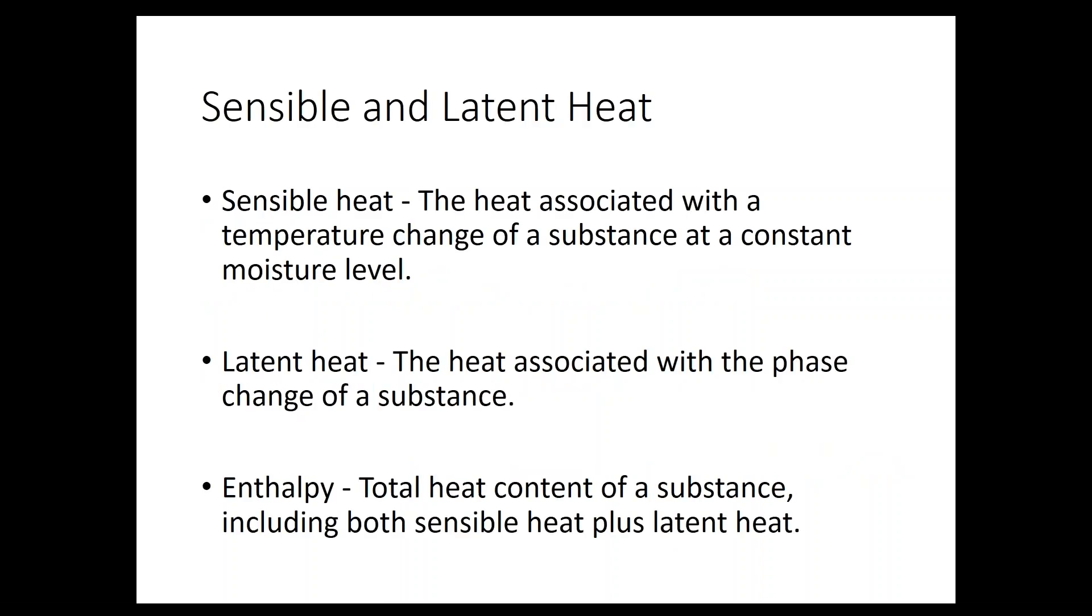Quick definitions: Sensible heat is basically the heat as if you would see it on a thermometer. It has nothing to do with the humidity of the air. Latent heat basically is the energy associated with the phase change of a material or changes in humidity. When you have more humidity, you have more energy in the air. And then enthalpy is the total of these two. It's the total energy density of the air or the water, basically the total energy density of a substance.